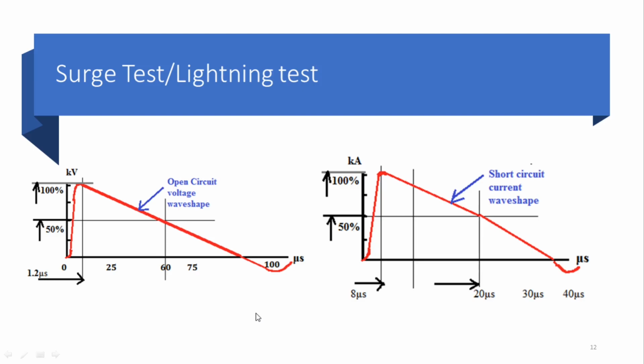When testing mains inputs, these surges are applied as a positive or negative voltage at all the zero crossings and the peaks in a cycle of the mains waveform. Time is allowed between each impulse to avoid overheating of the surge protection devices. Two generators are used to simulate surges in the main power line of the EUT via a decoupling network.